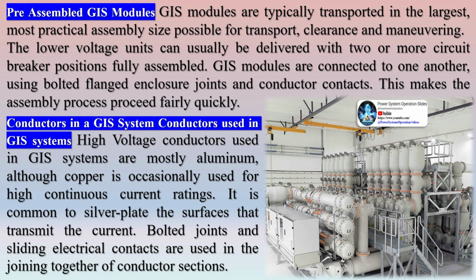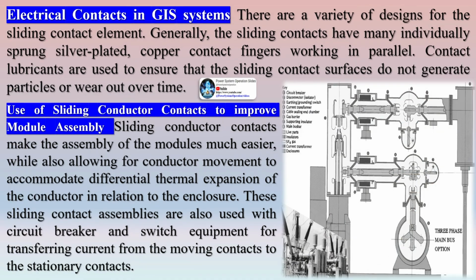GIS modules are typically transported in the largest, most practical assembly size possible for transport, clearance, and maneuvering. The lower voltage units can usually be delivered with 2 or more circuit breaker positions fully assembled. GIS modules are connected to one another using bolted flanged enclosure joints and conductor contacts. This makes the assembly process proceed fairly quickly.